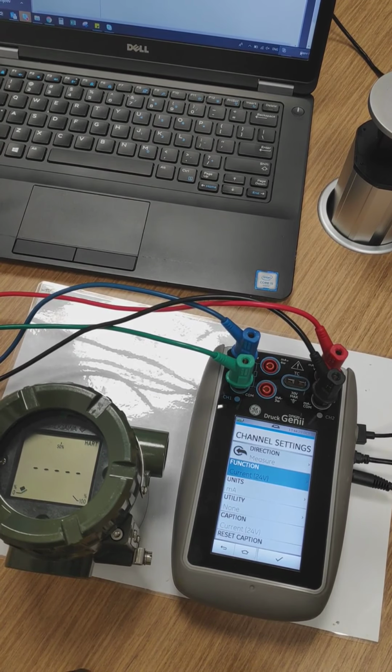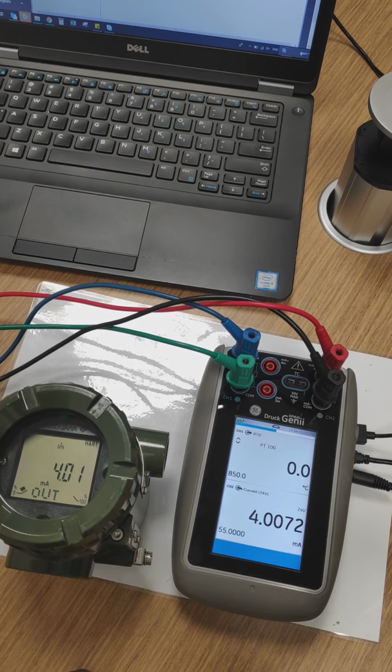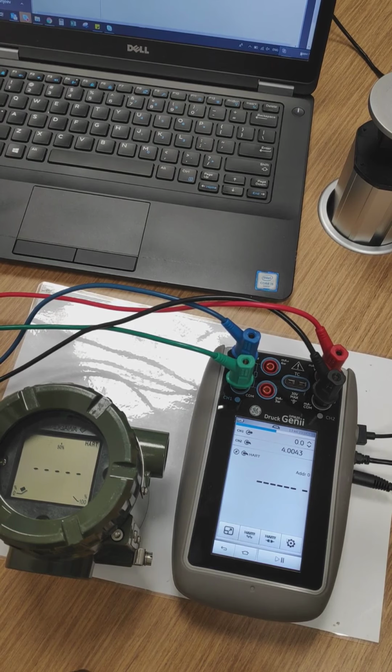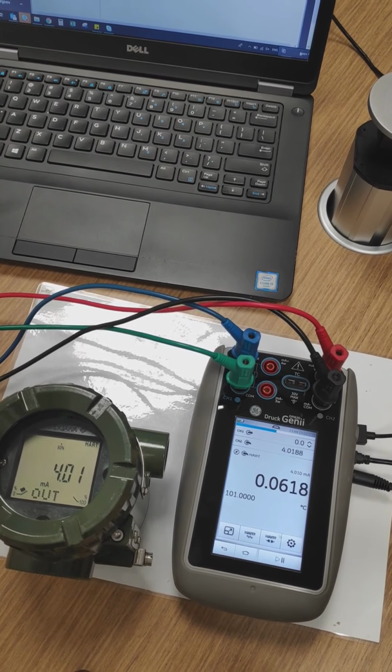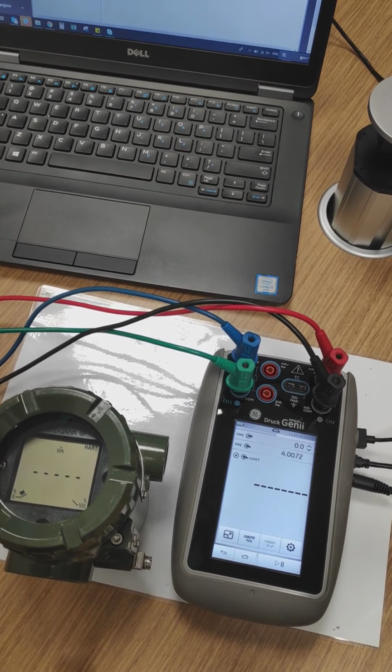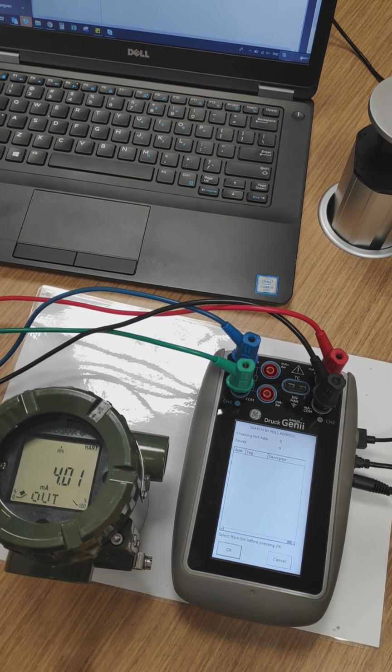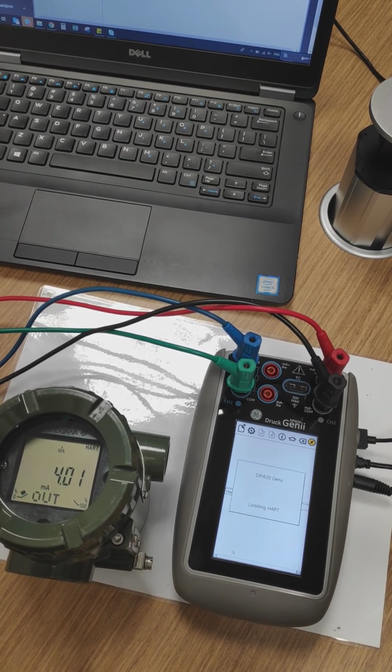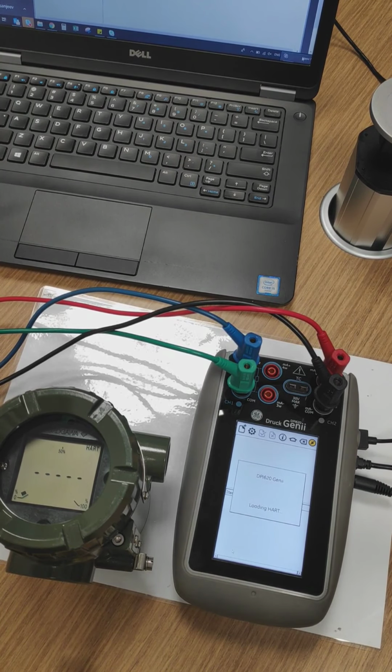And I need a HART resistor, which is necessary because we don't have a HART resistor in the test leads here. So in the settings, the resistor is already there. Okay, so we can start, wait for the HART function to start, and so we got that on address 0. Great.